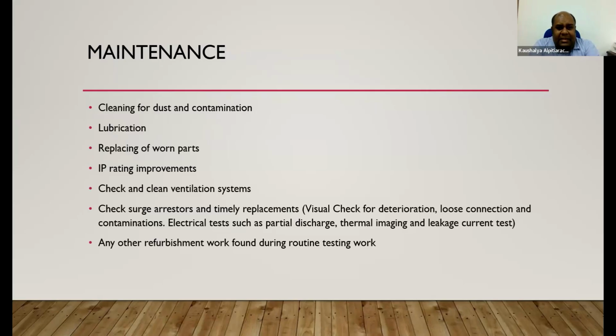Maintenance: cleaning for dust and contaminations, lubrication of mechanical parts, replacing worn parts, maintaining IP ratings and necessary improvements. Check and clean your ventilation system. Check surge arresters timely and replace. Visual checks for deterioration, damages, loose connections and contaminations at connection ends, and electrical tests such as partial discharge, thermal imaging, leakage current, or maybe insulation. Any other refurbishment work found during routine testing work.